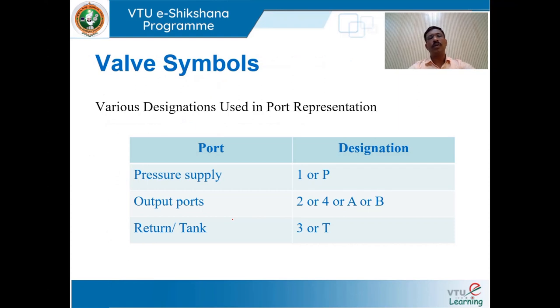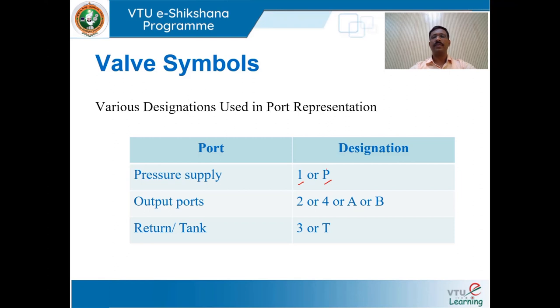We shall move on to valve symbols and discuss how the ports are designated. For the pressure supply port, it is designated as 1 or P. For output ports, it is designated as 2, 4, A, or B. For the return or tank line, it is designated as 3 or T.